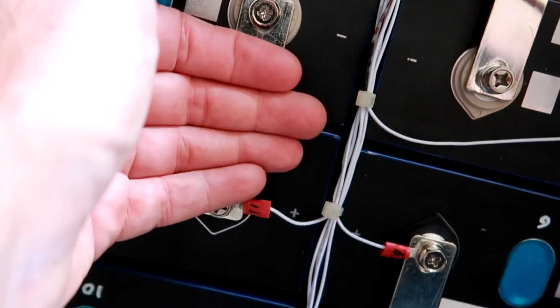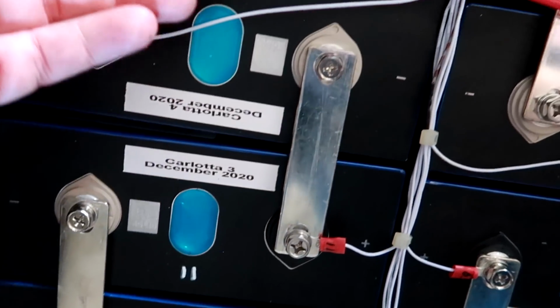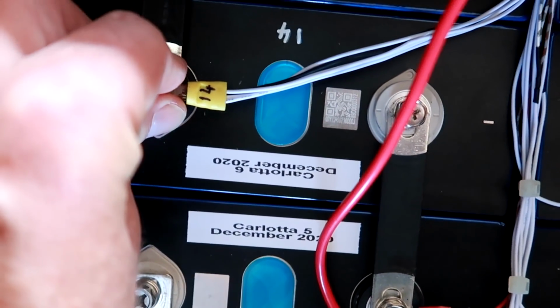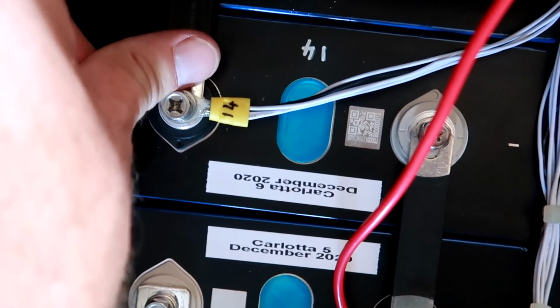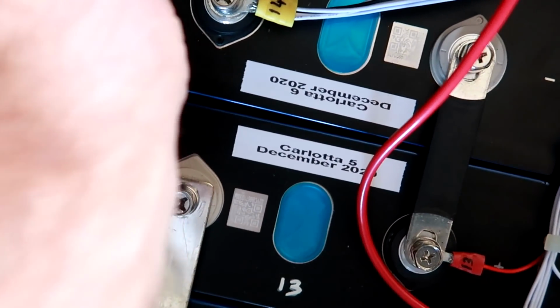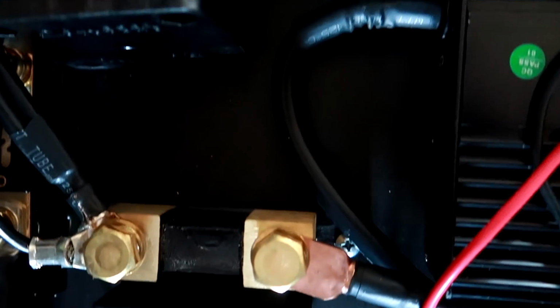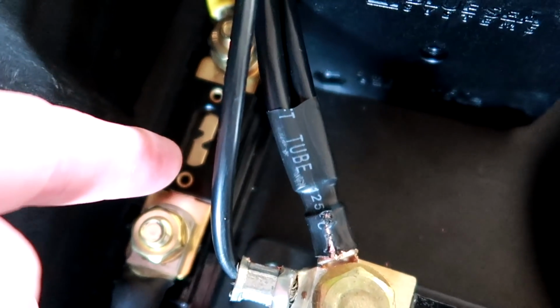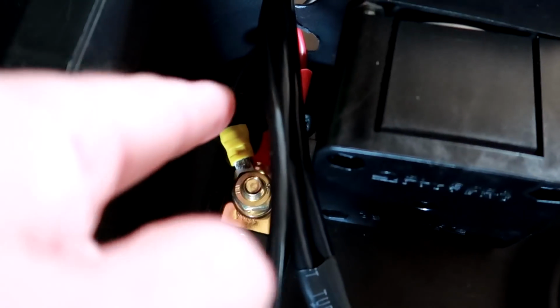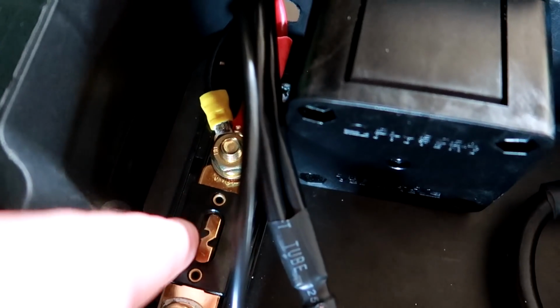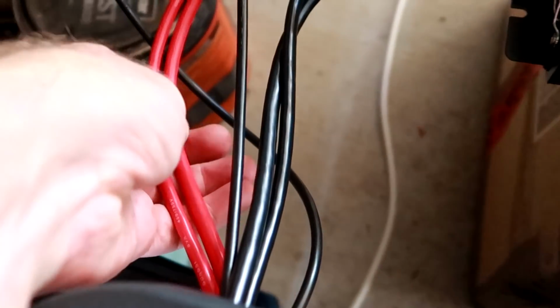This is 50 degrees, everything else stays cool. The bus bars are cool, apart from this one terminal, but it's not super hot, just a bit warmer than the rest. This is all warming up. This cable is warm, this cable is cold, and that's only because of the fuse. The copper cables are guiding the heat away from the fuse into the cables, that's why they heat up.